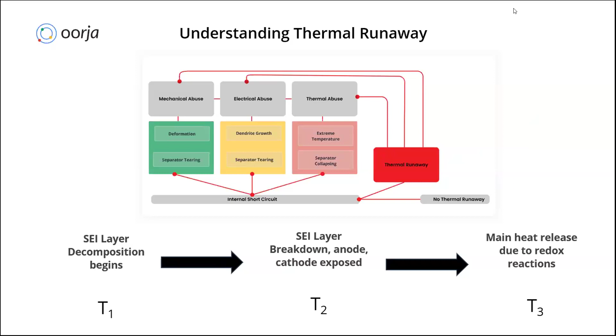Degradation also affects the thermal runaway signatures. As mentioned, there are three characteristic temperatures T1, T2, and T3 for any given cell. T1, the onset of self-heating, is typically around 70 to 90 degrees Celsius. T2 is around 140 to 200 degrees Celsius. T3 is the maximum temperature the cell reaches during thermal runaway.